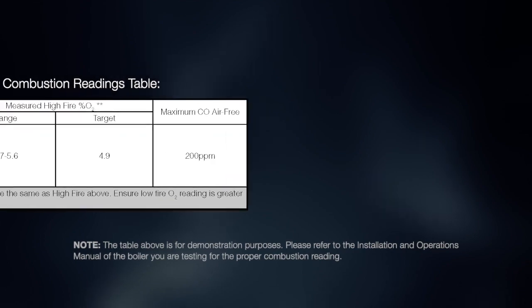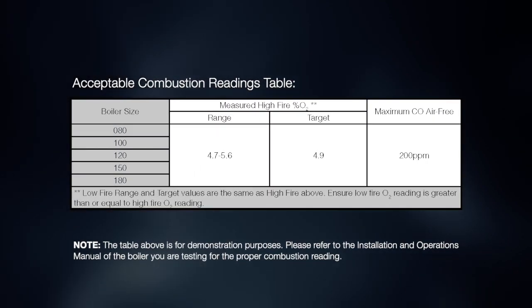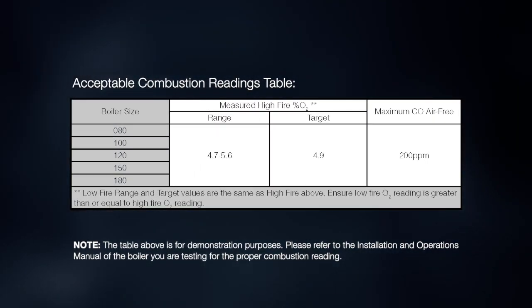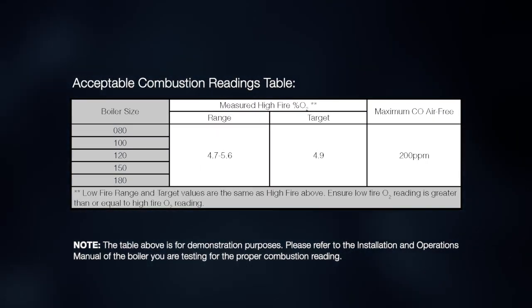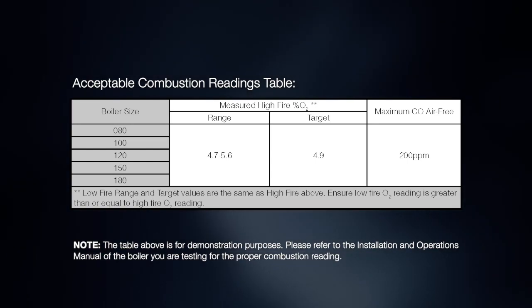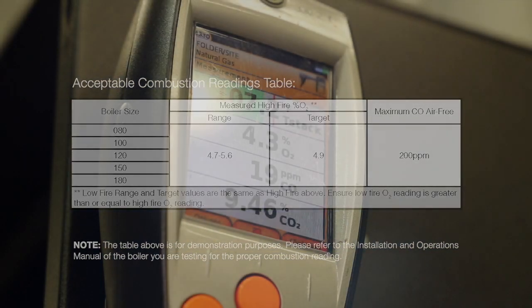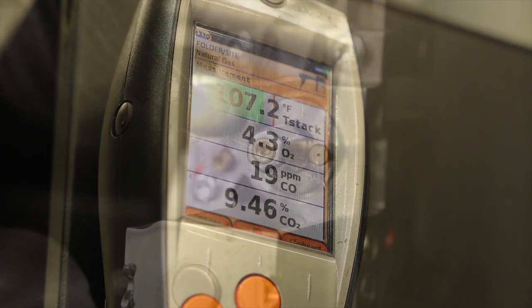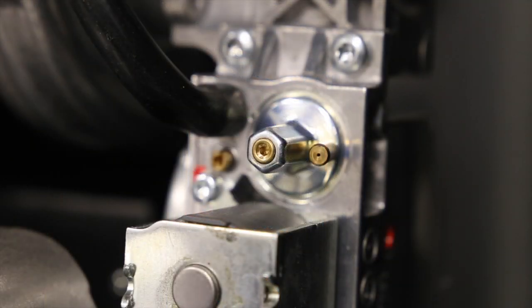Refer to the acceptable combustion readings table inside the installation and operations manual of the boiler you are servicing for the proper oxygen reading. If the oxygen level is not within the specified range, an adjustment to the offset regulator may be necessary.